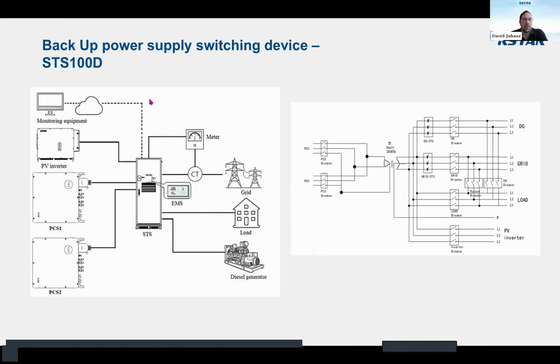The system has 2 operating modes in case of STS. For the on-grid mode, the purpose is to help to stabilize the grid for the supplier by starting the diesel generator and charging or discharging the batteries, and so to take part in the control and stabilization of the grid.